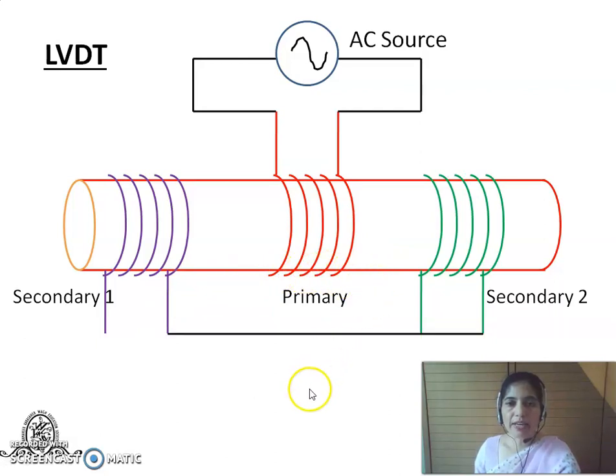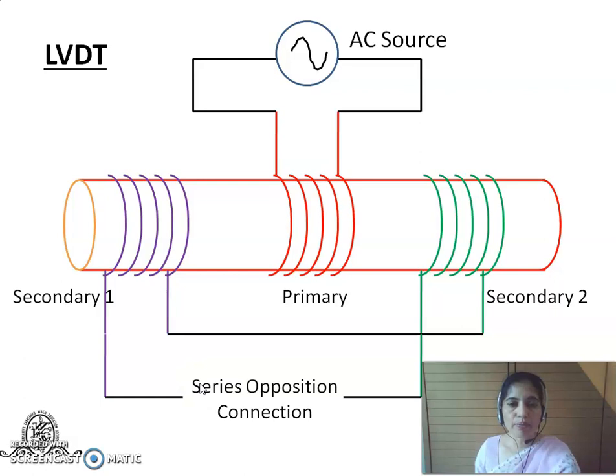These two secondary windings are connected in a series opposing connection. That is, one end of the secondary which is close to the primary is connected to the other end of the other secondary, which is far away from the primary. And the output voltage is taken between the other two ends of the secondaries. This type of connection is a series opposition connection. That is, the two secondary windings are in series, but the voltages induced in both of them will be opposing each other, and therefore they will be cancelling each other.